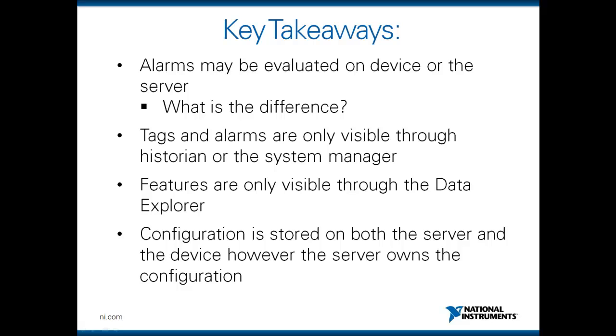Tags and alarms are only visible through the historian and systems manager. You can't look at tags and alarms in the Data Explorer. And features like TDMS file features are only visible through the Data Explorer. They are not visible through the historian or through the systems manager. If you want file properties to show up in either of those two places, then you can use the custom analysis VI and create tags for those features.